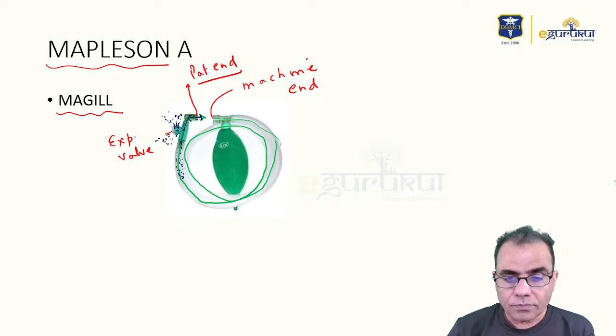Now, how much flow you should keep in each kind of circuit, that is how it is calculated, is much beyond your scope, but you have to know that for each kind of circuit you have to maintain this much fresh gas flow to prevent rebreathing. So, fresh gas flow recommendations for the Magill circuit, and as I told you, these recommendations are meant to prevent rebreathing.